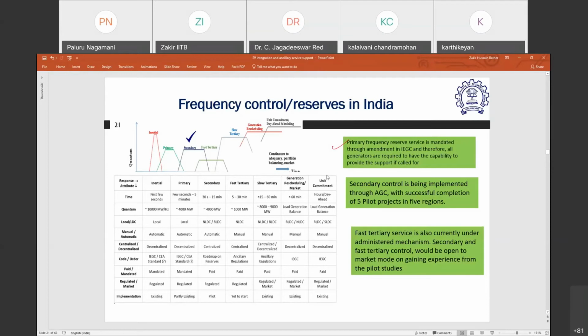Now, in the Indian scenario, how is this actually being ensured? The generators are not allowed to overload their generators. Therefore, in case there is a necessity, this primary frequency reserve, which is 4,000 megawatt in India, will actually be supplied by these generators by overloading the machine, the generator, for a short time. So this primary reserve is ensured through the overloading capability of the generators, but they are not getting paid for it. Secondary control is in the process of implementation.